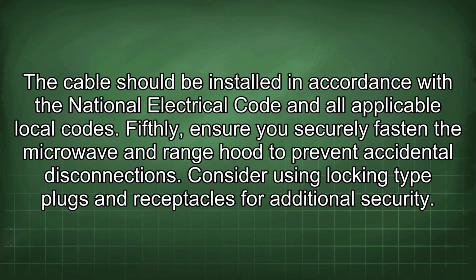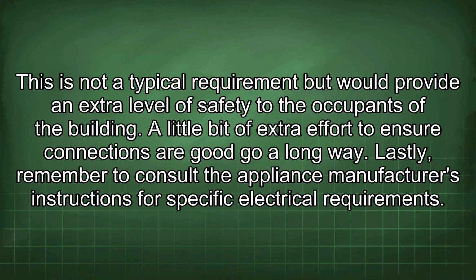Fifthly, ensure you securely fasten the microwave and range hood to prevent accidental disconnections. Consider using locking-type plugs and receptacles for additional security. This is not a typical requirement but would provide an extra level of safety to the occupants of the building. A little bit of extra effort to ensure connections are good goes a long way.